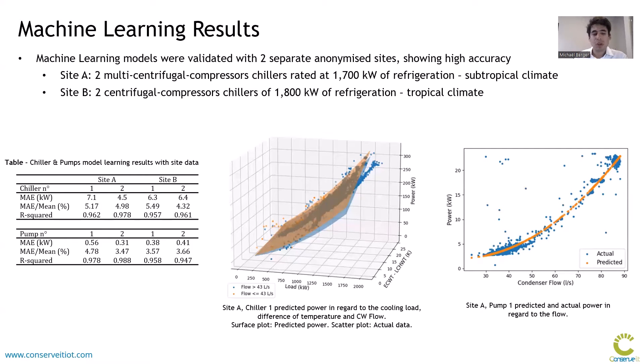Machine learning results for those equipment models were validated with two separate anonymized sites, showing high accuracy as seen in the table on the bottom left, with R-squared values of 0.95 or above showing a good fit between the models and the data. This can also be seen in the graphs of the chiller model showing the trend of chiller power usage as a function of the input variables, and similarly with the pump model showing for a specific pump the predicted and actual power with regard to flow.